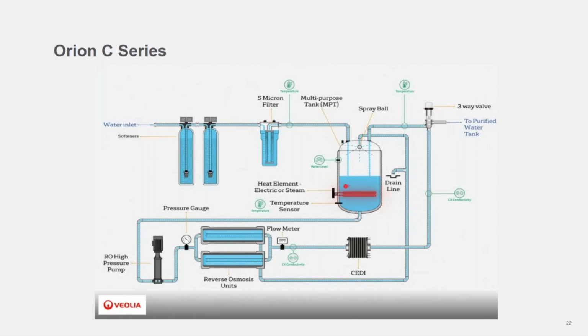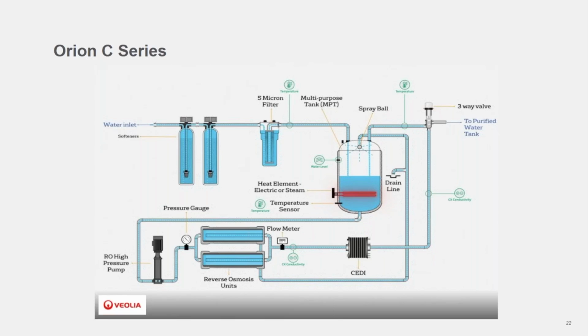It also houses the heating element, which could be electrical or steam for hot water sanitization. So we can sanitize the RO, EDI right up to the three-way valve sitting on the top of the purified water tank and back into the tank again. So that's the cycle for hot water sanitizing. And as you can see, there's a number of sensors around the system. During hot water sanitization, we map the heat element of it. So the temperature sensor, as we can see there at the bottom of the multi-purpose tank. There's a temperature element on the outlet of the CEDI combined with the conductivity cell, and on the return line there as well, there's a temperature sensor. So it's a 3 mapping point in terms of hot water sanitization on these units.